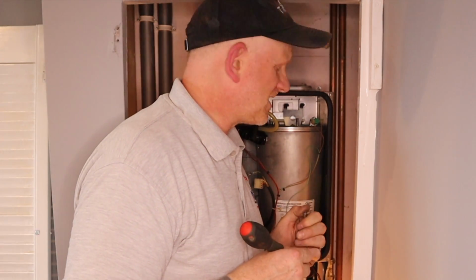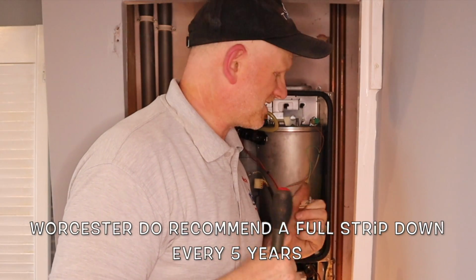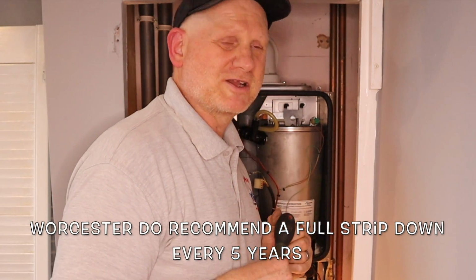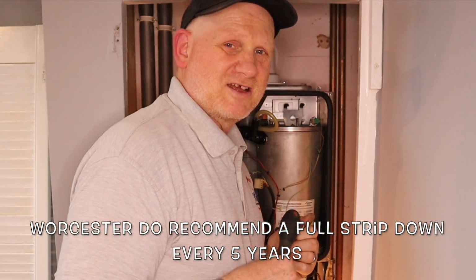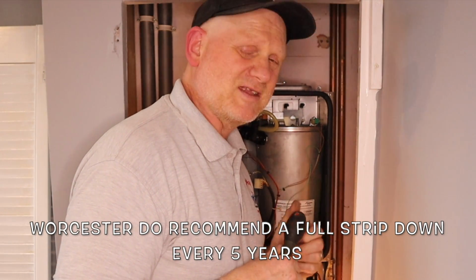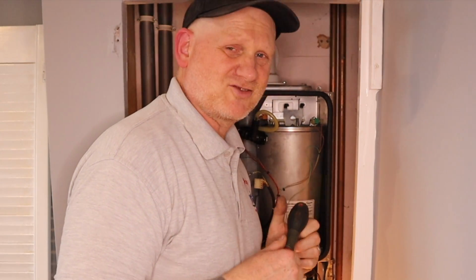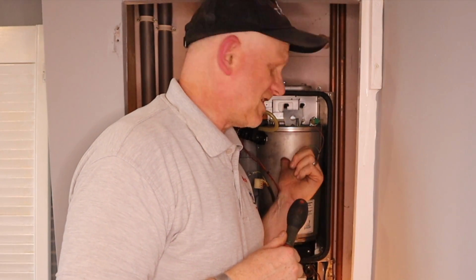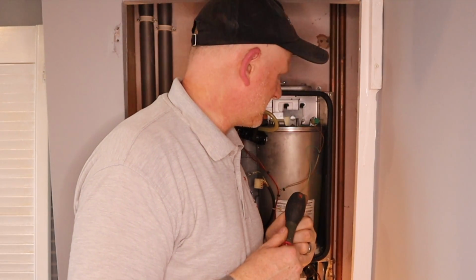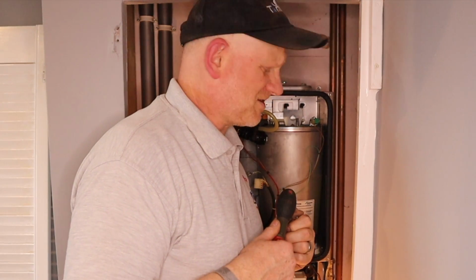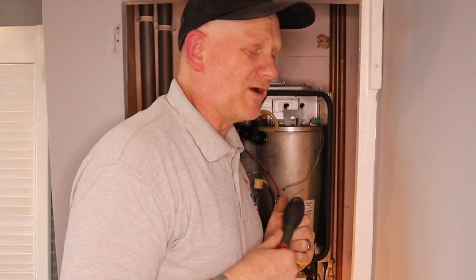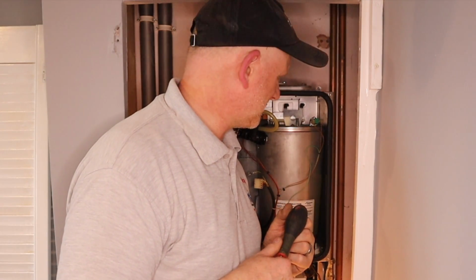Now the manufacturers say if the fan pressure test passes, you don't need to strip and clean it. But if you don't strip and clean it on a regular basis, you can't get the beggars out, and it ends up with a new heat exchanger. Now luckily enough, I've got about 3 or 4 of these at the training centre, and the ironic thing is every one of the baffles come out on the ones in the training centre.